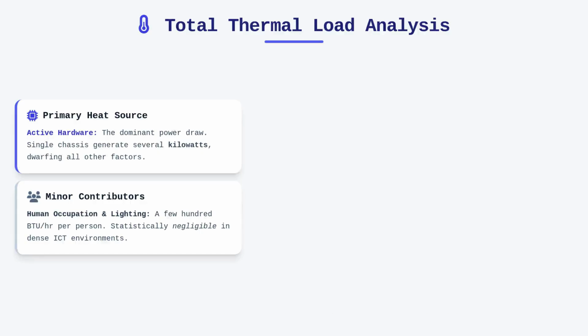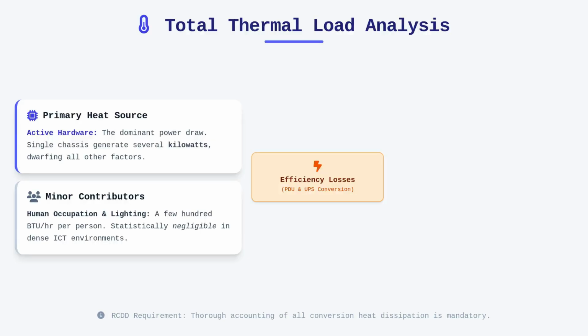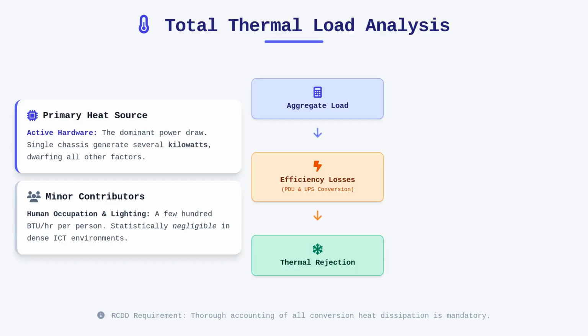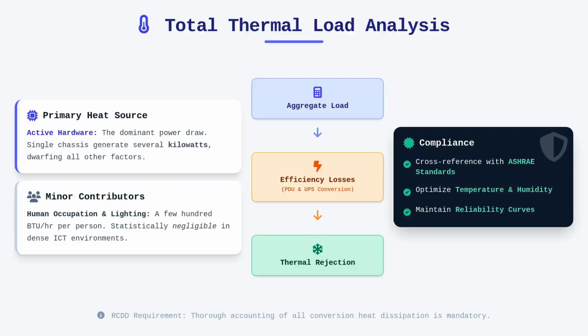Nevertheless, an RCDD must be thorough in every calculation, incorporating the inefficiencies of power distribution units and uninterruptible power supply systems into the total thermal budget. A UPS is never perfectly efficient, and the energy loss during the conversion process is dissipated as heat within the room itself. By aggregating the total electrical load, including the inevitable efficiency losses, we define the minimum thermal rejection requirement. We then cross-reference these requirements against the ASHRAE standards for temperature and humidity to ensure the equipment operates within the specific reliability curves specified by the manufacturers.